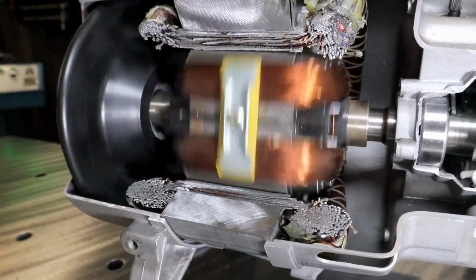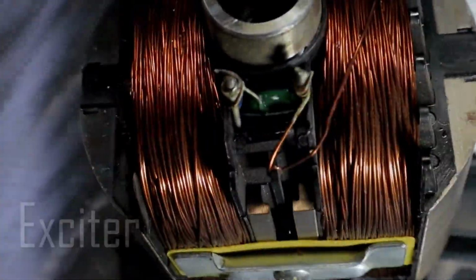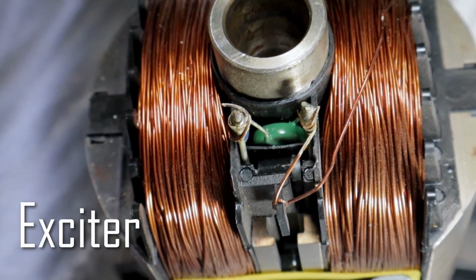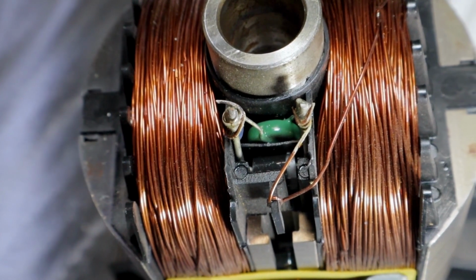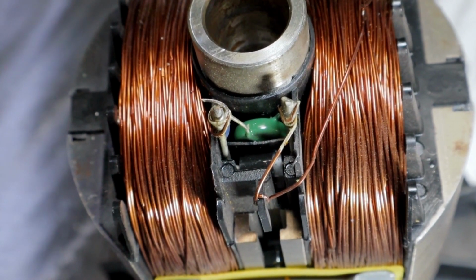Now, in this case, there's no permanent magnets. It's an electromagnet. So now within the rotor is an exciter. An exciter produces enough DC voltage to charge up the coil and makes it magnetic.